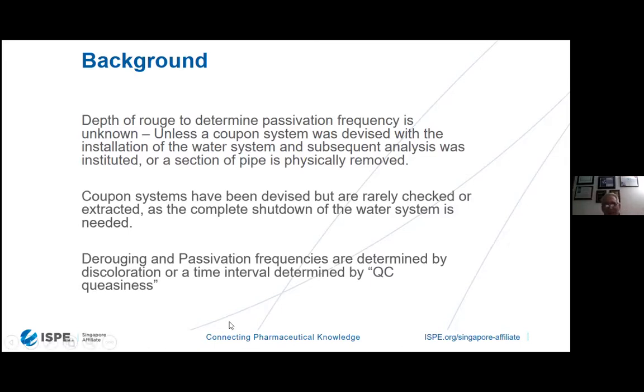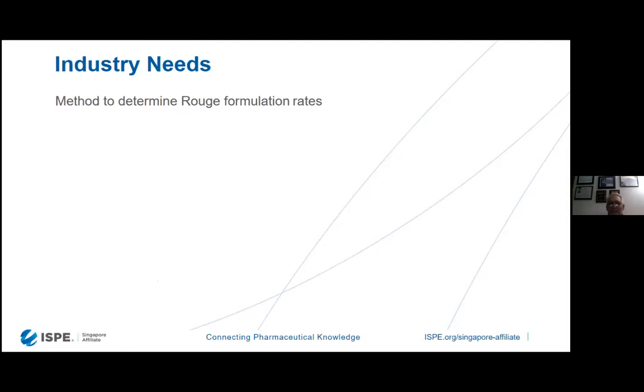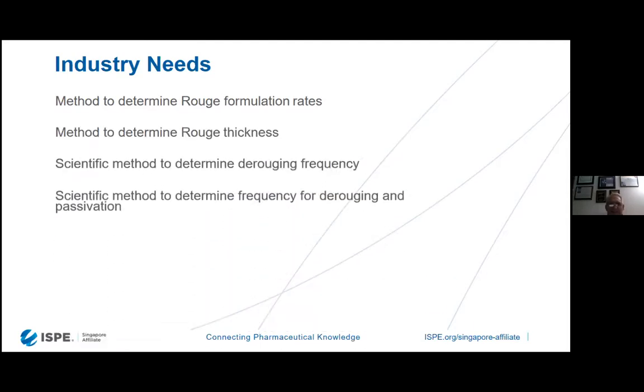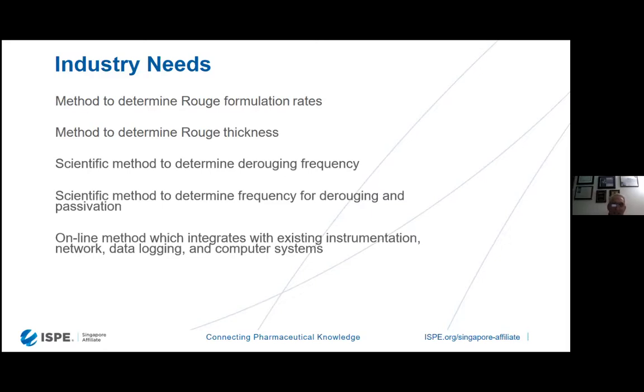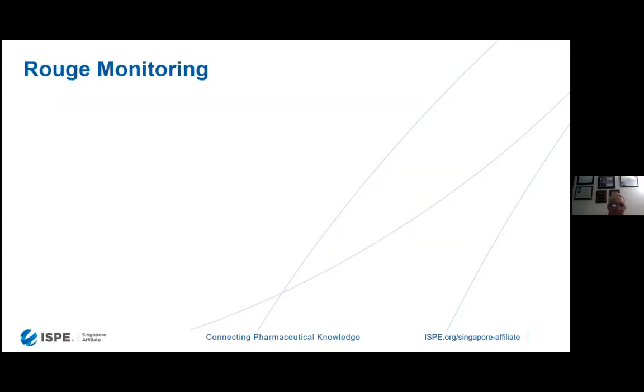The point is that by doing that, by setting up frequencies that are based on discoloration or a time interval with no scientific data, you're probably wasting a tremendous amount of money in chemicals and in downtime. The industry needs a way to determine formulation rates, thickness rates, development over time, a scientific method that should be integrated to determine frequency, and also determine when to actually do derouging passivation and what the needs would be. It should be an online instrument that integrates with all the rest of your existing online instrumentation. All water systems today are completely automated. They're completely computerized. And this is another device, an instrument, which can be installed and integrated into your computer system as it exists today. Should be easy to calibrate and maintain.